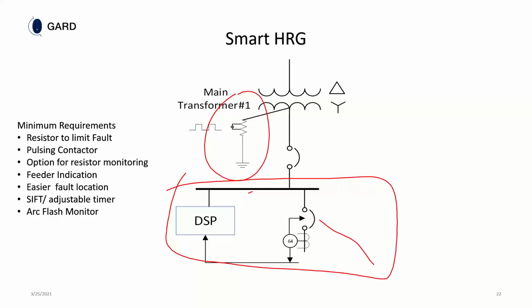You have an option for resistor monitoring. One of the things that's in the Canadian Electrical Code is that you have to monitor the resistor for electrical integrity, which is not necessarily performed in the United States. It's easier to find the fault. We have an adjustable timer. So we've had some customers that say, I'm going to give my electricians 8 hours to find the fault. If they don't find the fault in 8 hours, I'm going to trip this device. Just so the electricians have something to do, I would imagine, because electricians are always busy. But if you say they don't have to do anything when there's a fault, they will not do anything when there is a fault. If you give them a time limit of clearing that fault, now they'll go out and find it.